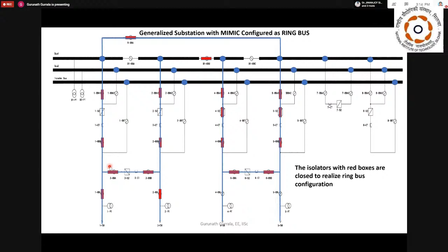I will show you how the panel looks from the bottom to the top. At the bottom, you have the buses, I would say bus 1, bus 2, bus 3, and then you have your isolator. Then you have the CTs. In order to minimize the cost, we only populated the minimum number of cores that are needed. So here you can see in this table, the last point, whatever number of cores are required, that many we have populated.